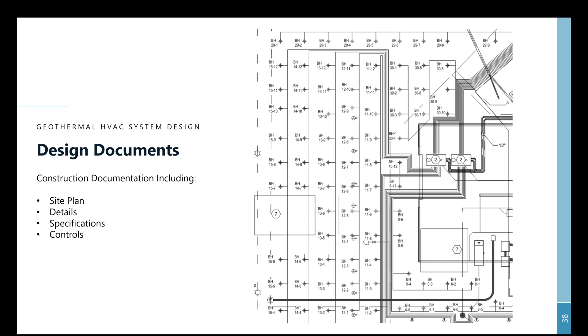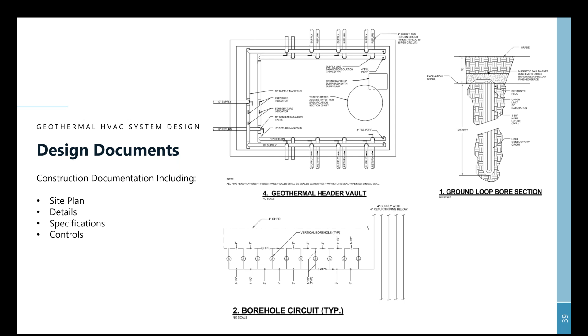In a significantly large bore field, running each circuit horizontally back to the building would mean routing quite a number of circuits. The vault allows you to take all those circuits and simply send two pipes—a supply and return—back to the building, which helps economize on how much space we're taking up on the field.